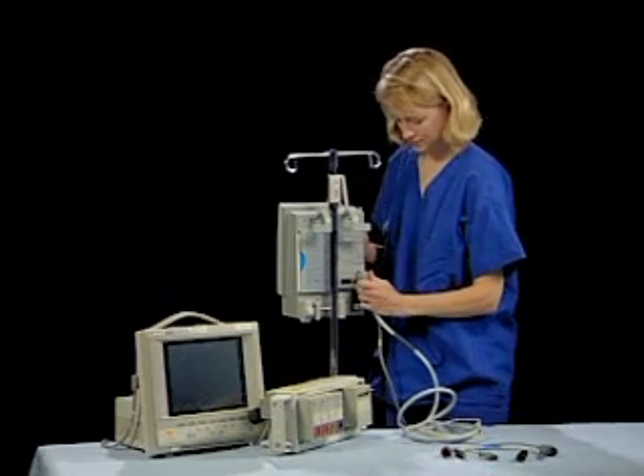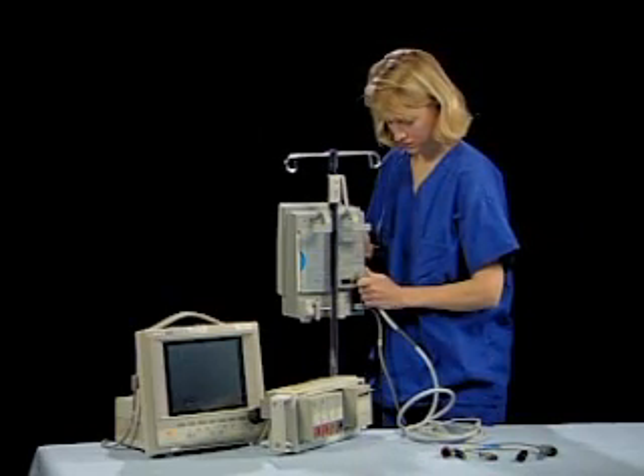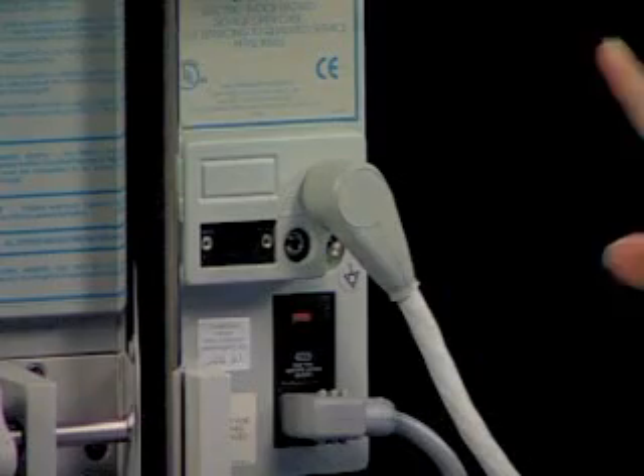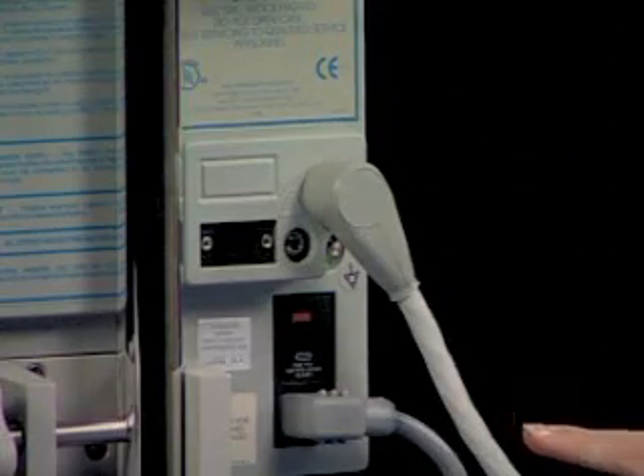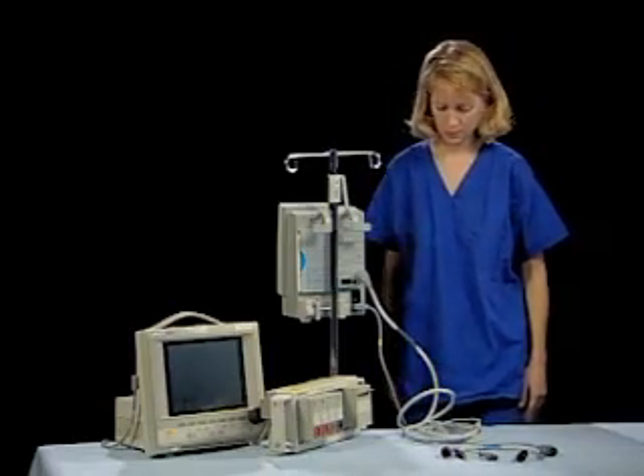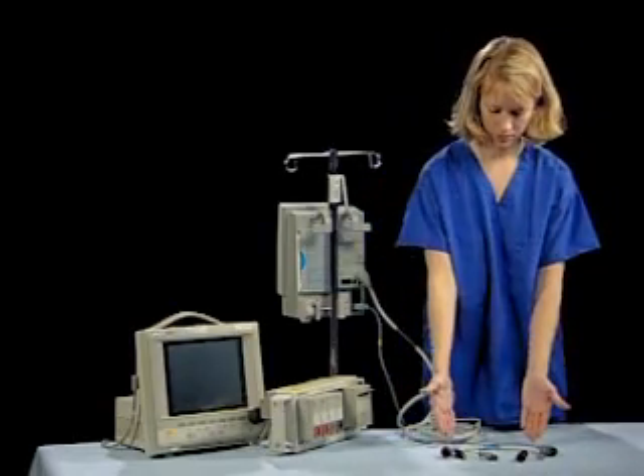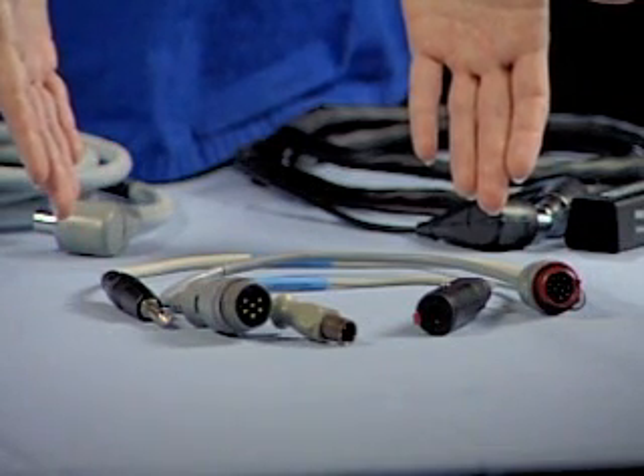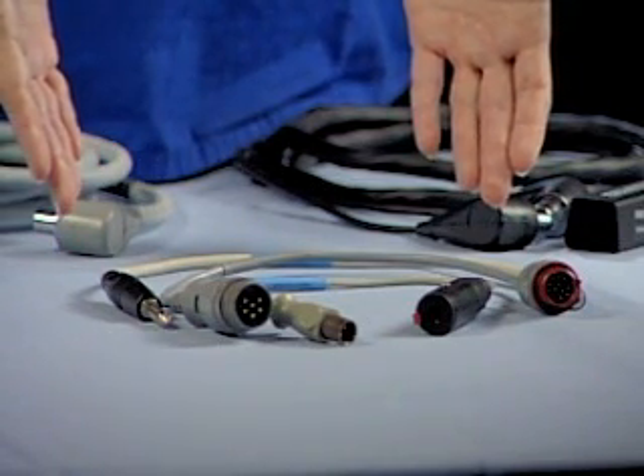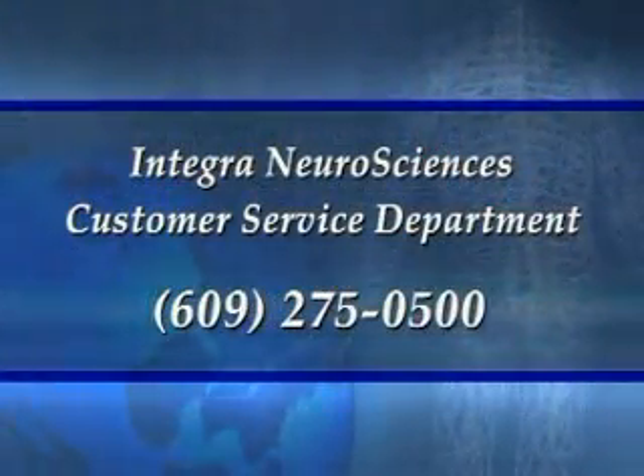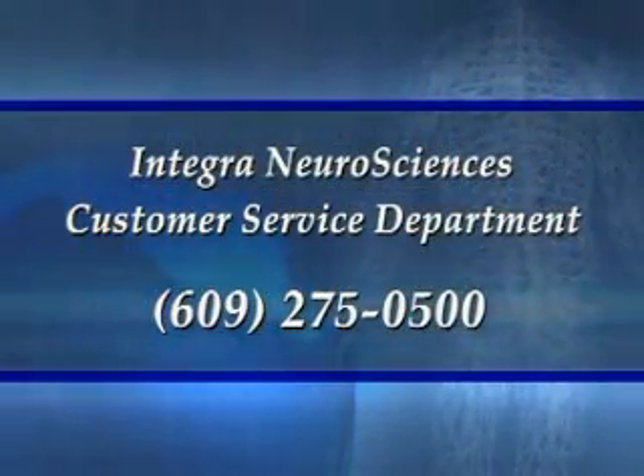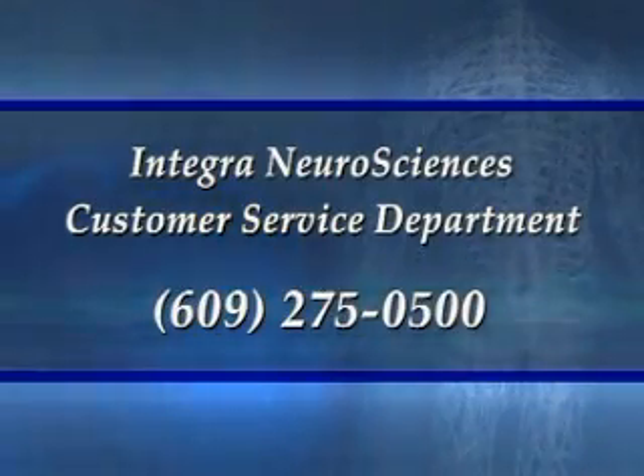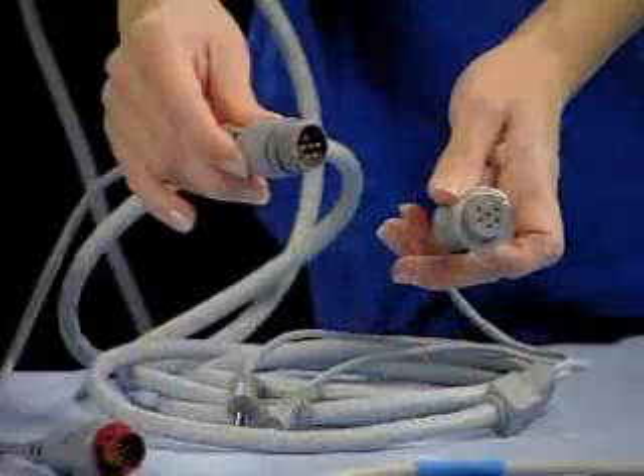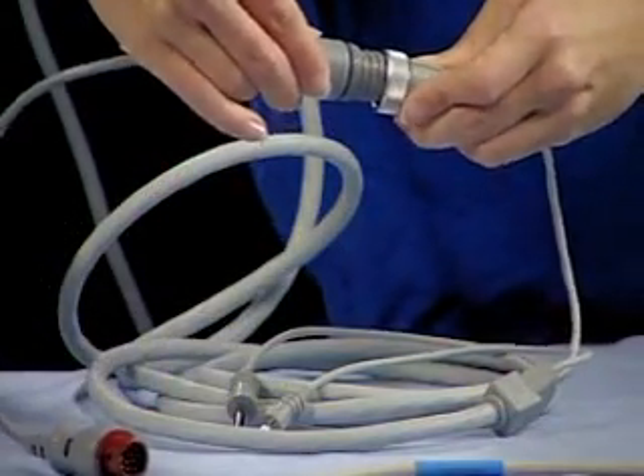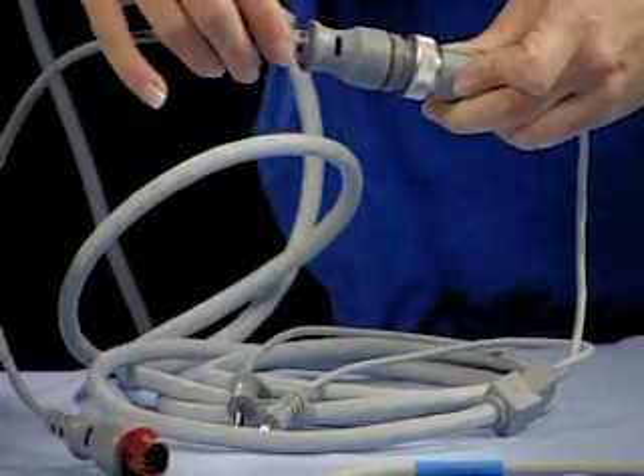Connect the patient bedside monitor cable, PMIO MPM, to the back of the MPM-1. Note that it goes in at a 45-degree angle. The patient monitor cable connects to your bedside monitor with the use of adapter cables specific to your bedside monitor. These are packaged separately from the MPM-1 and should have been ordered with your MPM-1 monitor. If not, call Integra Neurosciences customer service with your bedside monitor model number to order the correct adapter cables. The large round cable connector on the gray PMIO cable is attached to the appropriate adapter cable and is then connected to the pressure port on the bedside monitor.